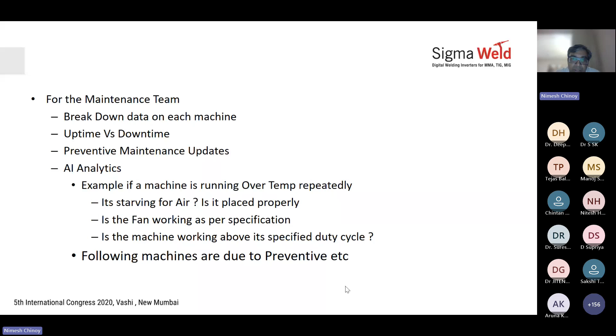So if the machine shows over temperature repeatedly, a message can pop up to the maintenance team saying this machine has been showing over temperature error for the last 7 days. Can you check if it's placed properly? Can you check if the fan is working? Can you check if the machine is working as per the specified duty cycle? This makes it very easy for the maintenance guy to find the root cause of the repeated failure. But if there's no data available for them to analyze, they will only find out each time what was wrong, correct it, and move out - and that fault may come again.